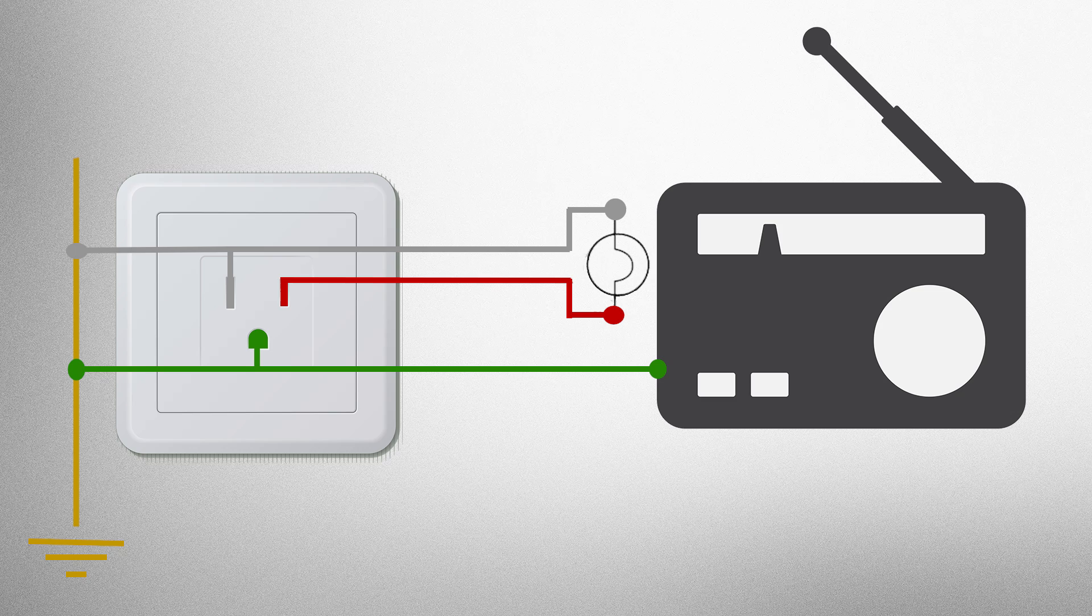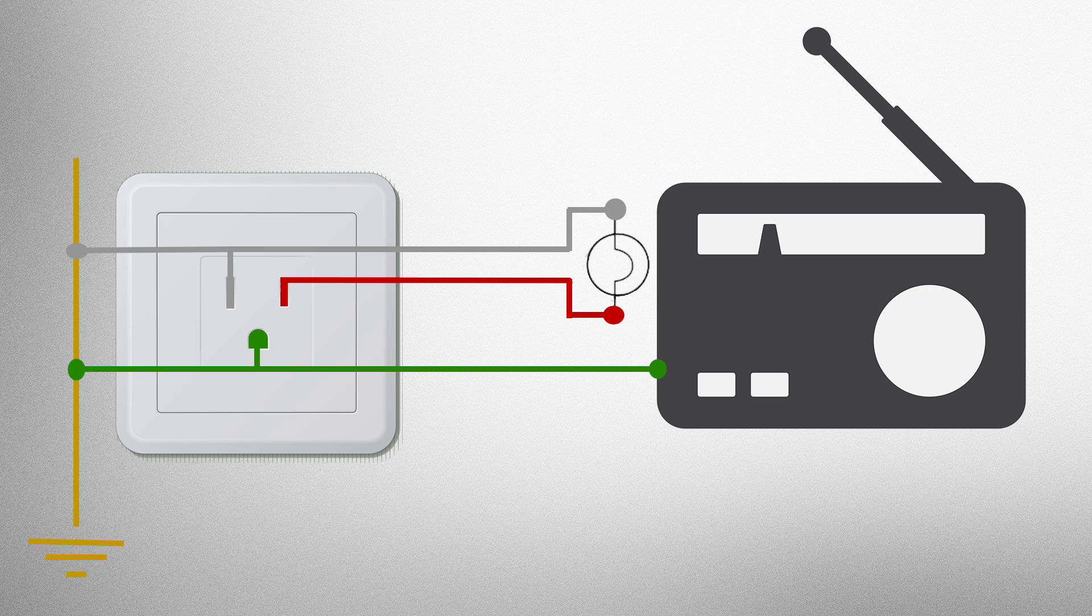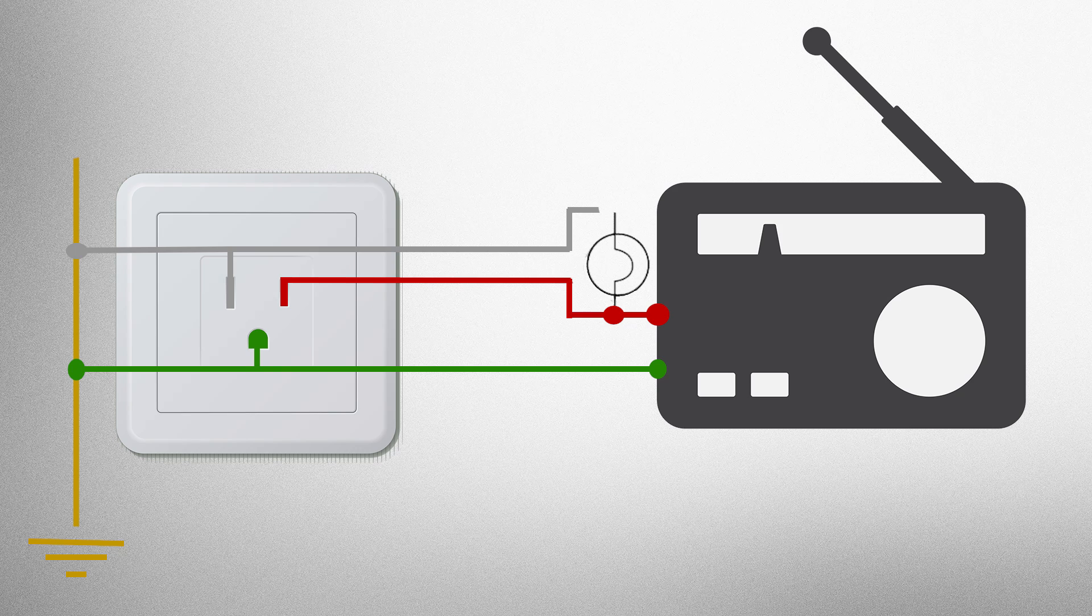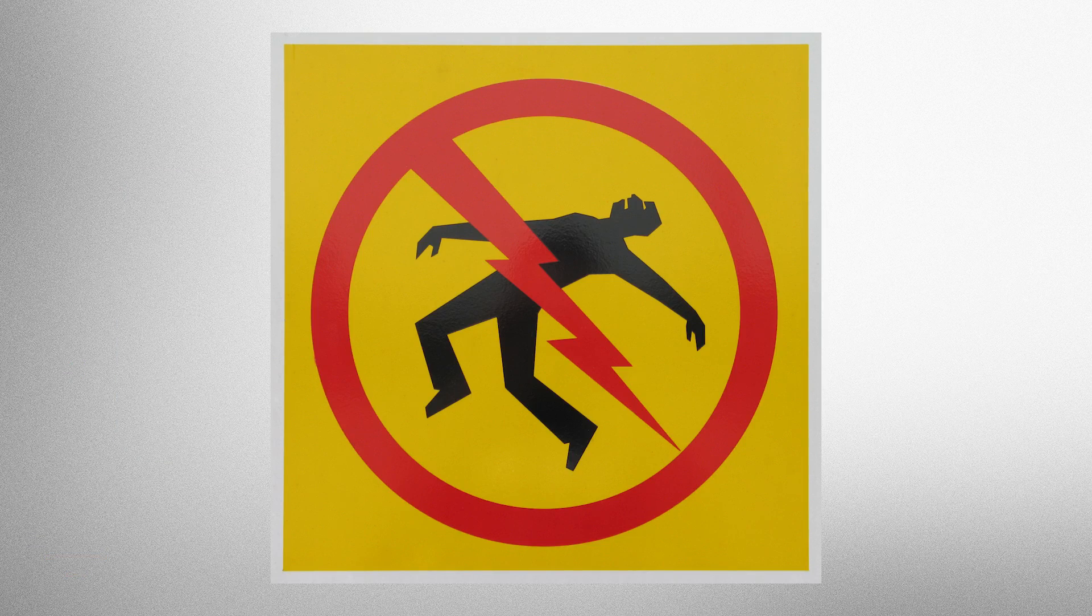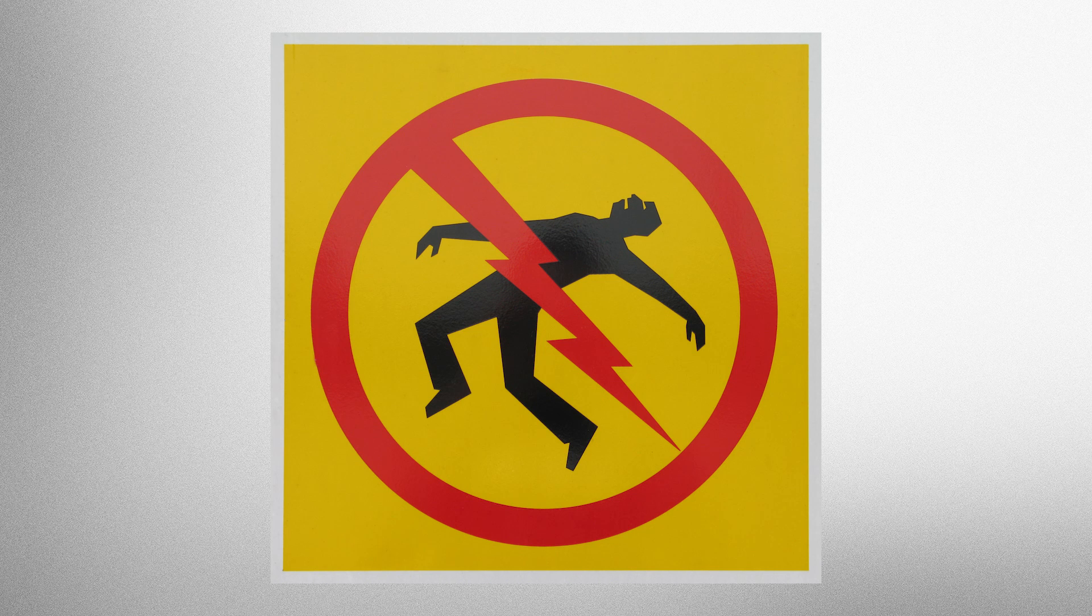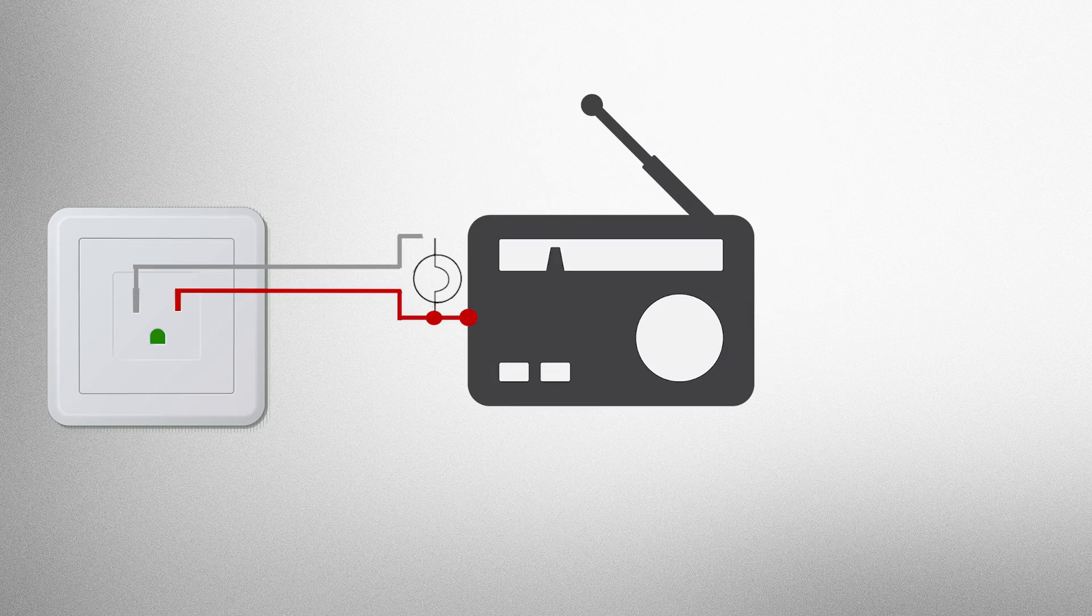So why have both a neutral and a ground when they both ultimately just tie to the earth ground bar in the main breaker box? Among a few other benefits, this is primarily so that if something should go awry with the device, like a stray hot or neutral wire coming into contact with the outer conductive parts of the device, for instance if the insulation wears away or wire comes loose, you don't die or seriously get injured if you touch the device and it's plugged in.